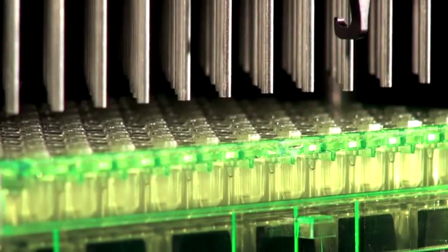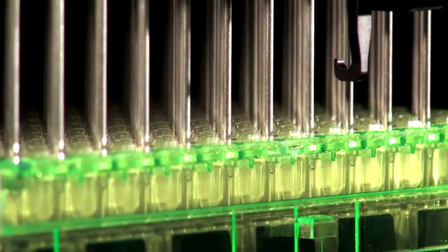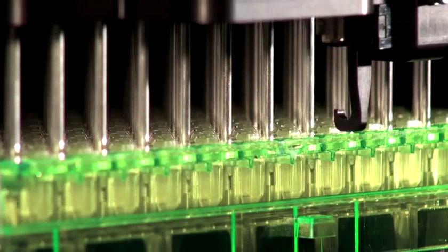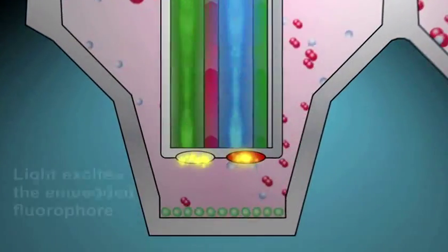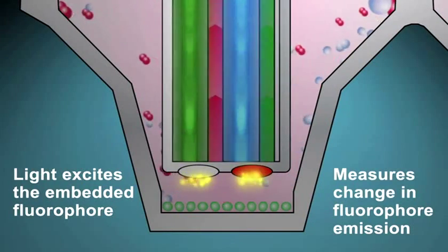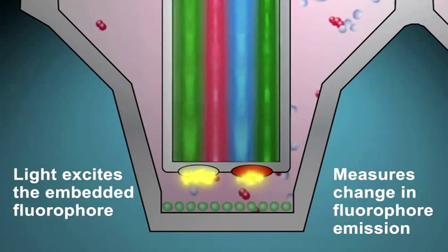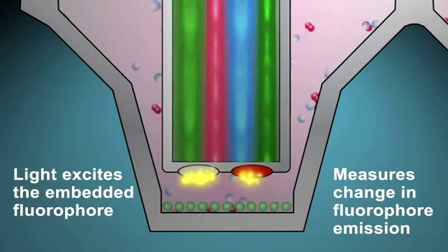Inside the instrument, fiber optic bundles simultaneously insert themselves into all the sleeves of the sensor cartridge. The fiber optics emit light that excites the embedded fluorophores and then reads back the change in fluorophore emission due to the change in oxygen and protons.